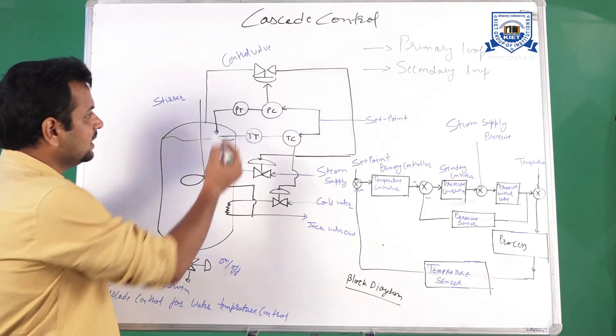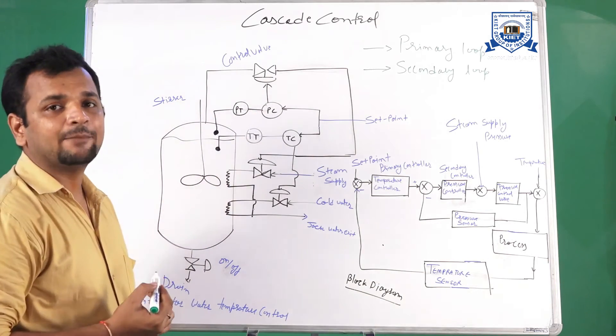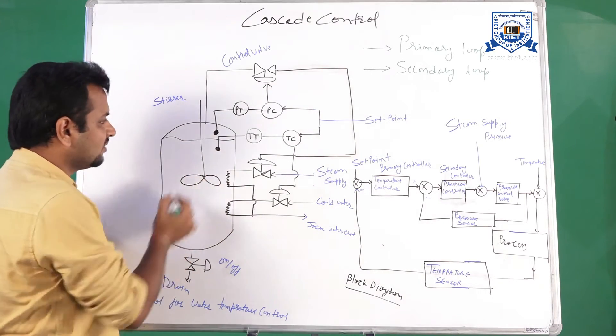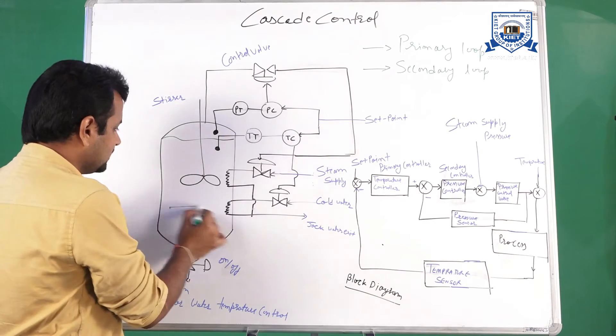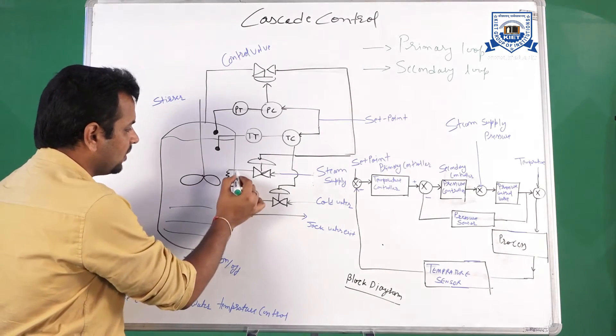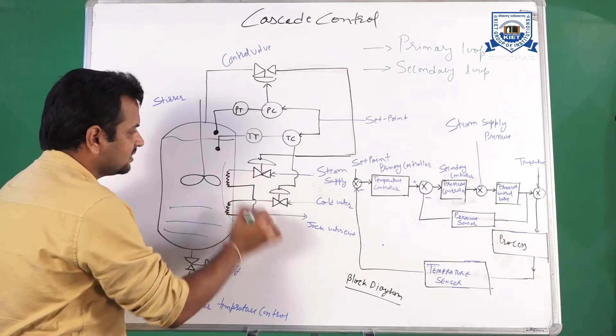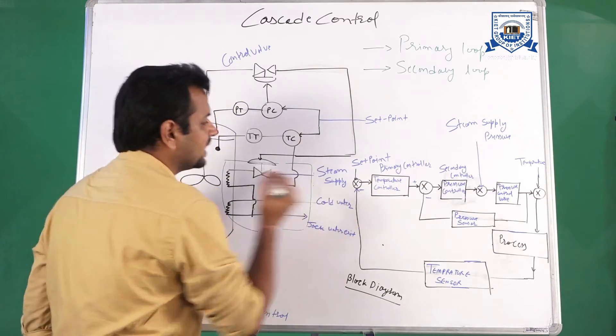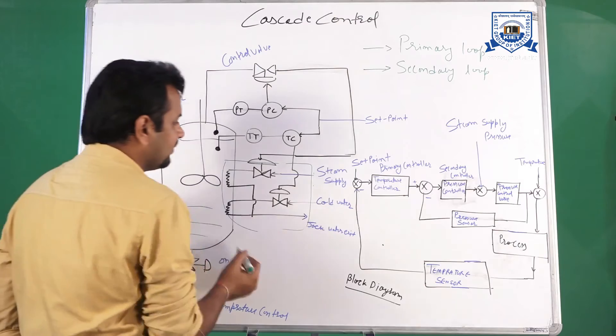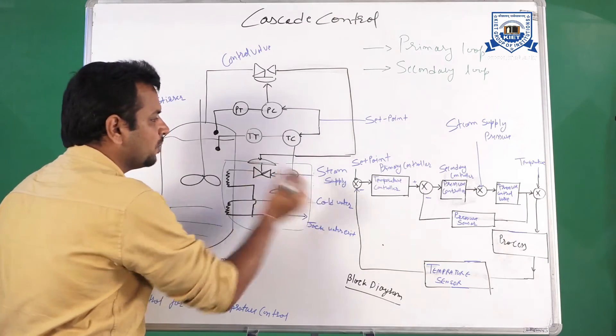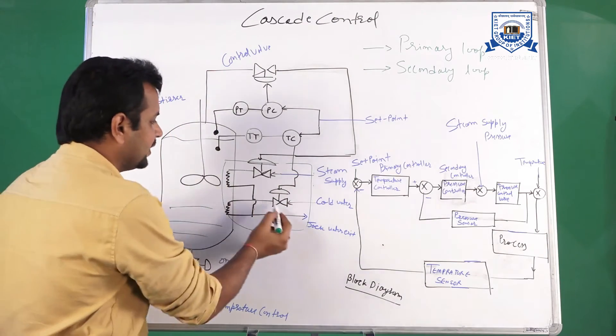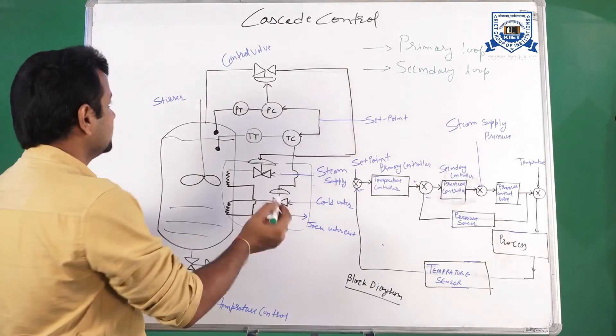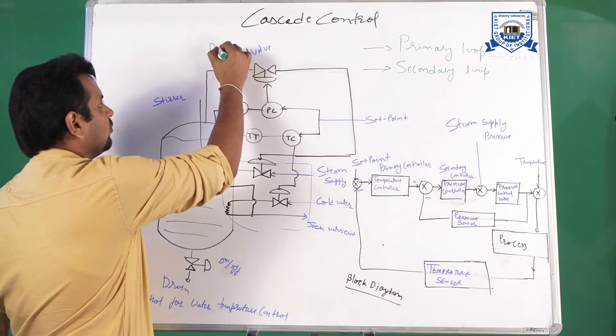In that example, we are controlling both pressure and temperature. As you can see in the diagram, there is a stirrer for mixing the product. This circuitry is for temperature control — there is a supply of cold water and a steam supply. To increase the temperature, I will open the valve of steam supply, and to decrease the temperature, I will open the valve of cold water. A pressure control valve is also there for controlling the pressure.